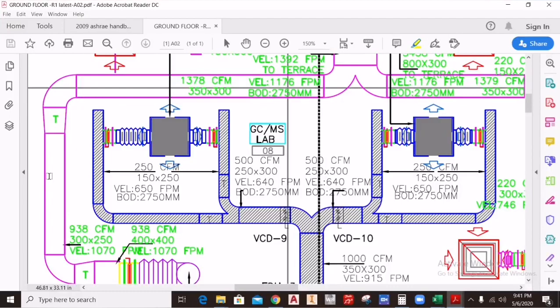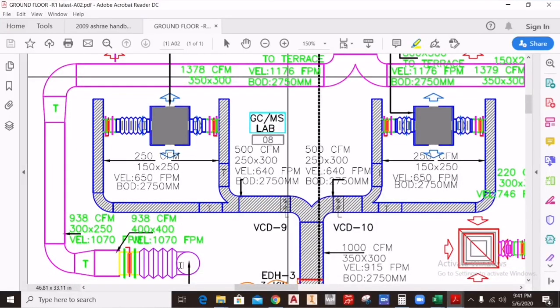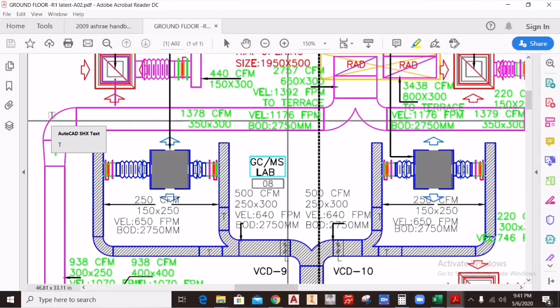These pressure losses in the fittings are considered to be the external static pressure. If you calculate all the pressure losses in your duct, that total will be your external static pressure. You need to calculate this for both your supply duct and your return air duct, since the fan is connected to both. Add the losses from both ducts together to get the total external static pressure of the AHU, exhaust air fan, or supply air fan.